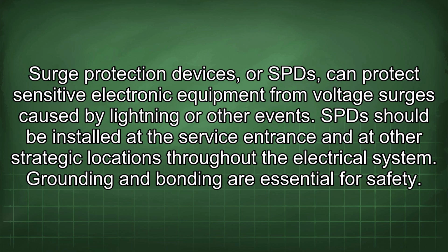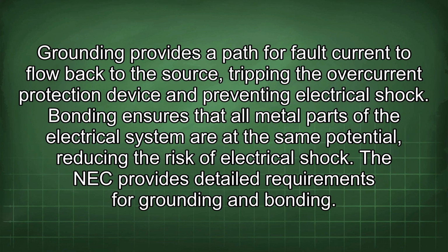Grounding and bonding are essential for safety. Grounding provides a path for fault current to flow back to the source, tripping the overcurrent protection device and preventing electrical shock. Bonding ensures that all metal parts of the electrical system are at the same potential, reducing the risk of electrical shock. The NEC provides detailed requirements for grounding and bonding.